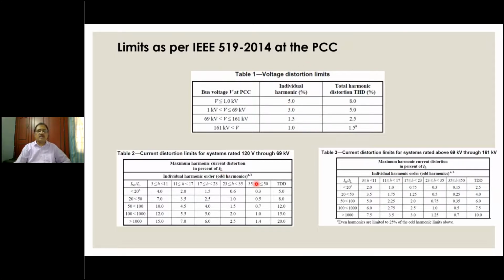For current, we have two charts. Up to 69 kV, this is not available even for household appliances. 120 volt, or 110 volt, is the voltage level for domestic in the USA. We have 230. So if this standard covers from 120 volt through to 69 kV, then it should cover domestic also. But this is not implemented for domestic or single phase industry supplies. It is 11 kV and above only. So in this chart, you will find 11 kV and above.